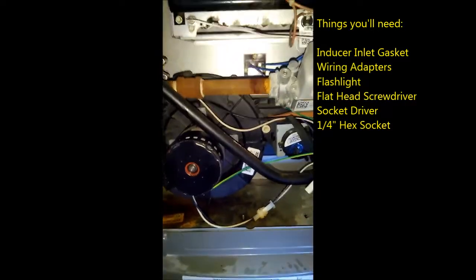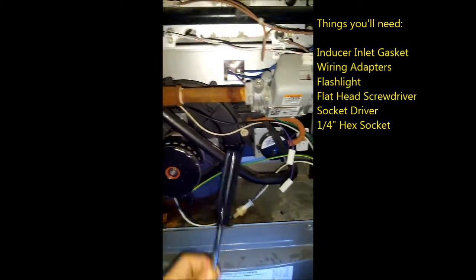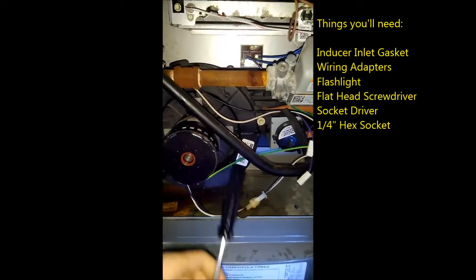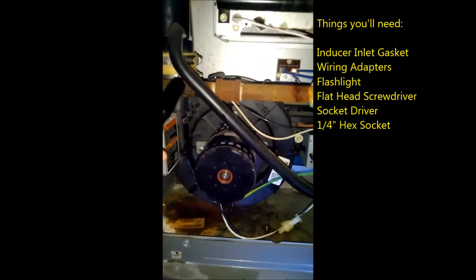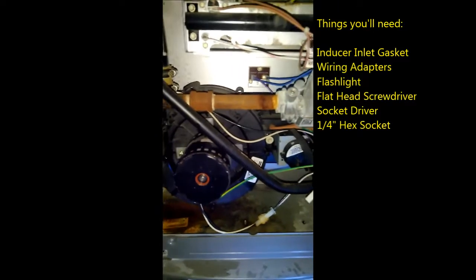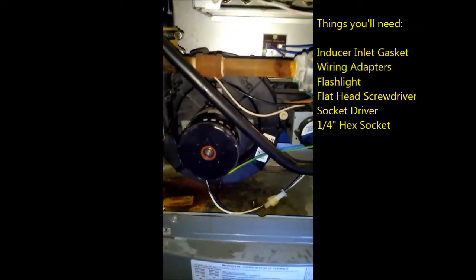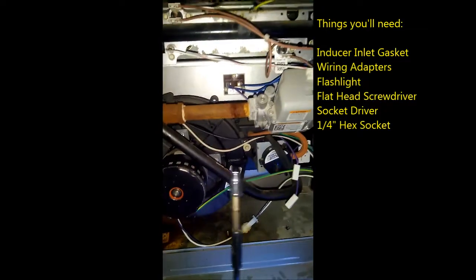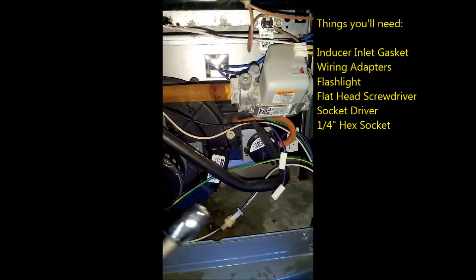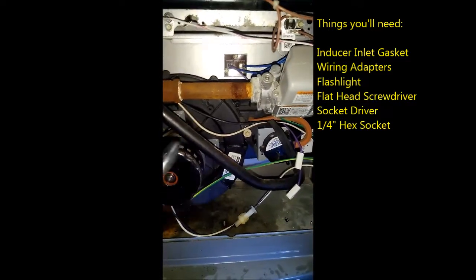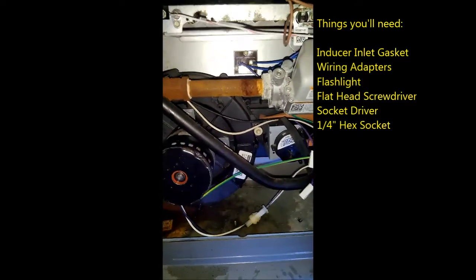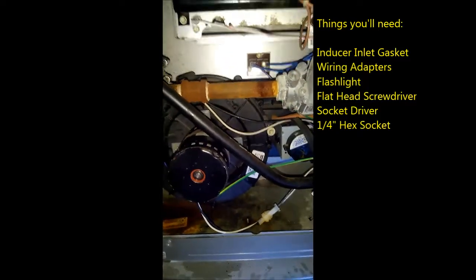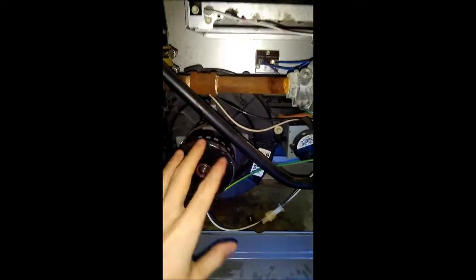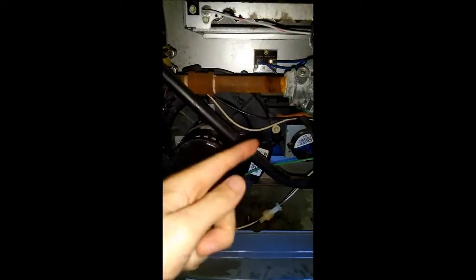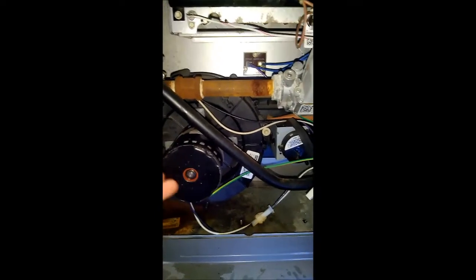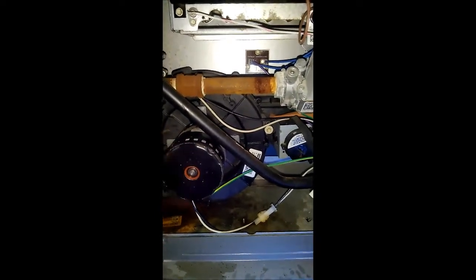And then other things you're going to need are obviously a flashlight, a flathead screwdriver to get to the hose clamps that are holding the ABS tubing on there, and also a socket driver with a quarter inch hex head bit on the end. That's for those fasteners over there. And basically, really, it's not rocket science. You're just trying to get things disconnected that are blocking the inducer assembly so that you can unscrew it and pull it out, remove the gasket, replace the gasket, put the new one in its place and reassemble everything.